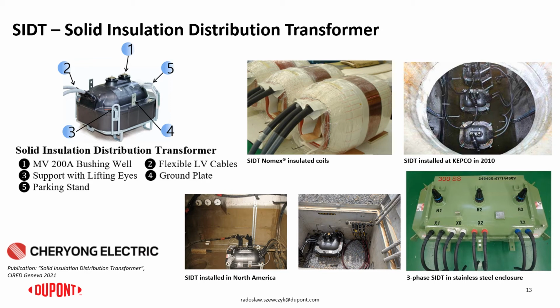Like we could hear that in California, a significant part of the distribution grid will be buried underground to avoid the exposure to the forests and eliminate or reduce the risk of the fires. Such transformer, what we call SIDT, solid insulation distribution transformer, in the underground vault, could be a good solution for those networks where the fire safety must be improved.